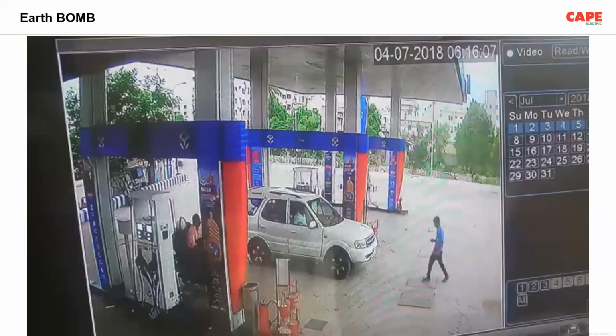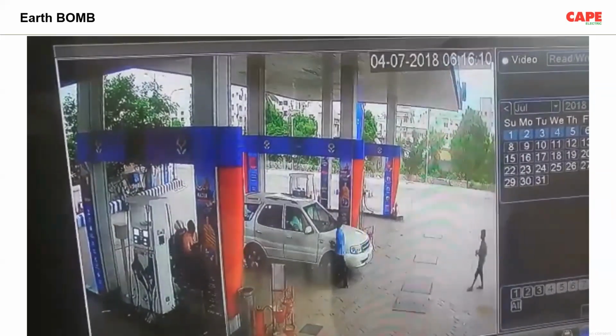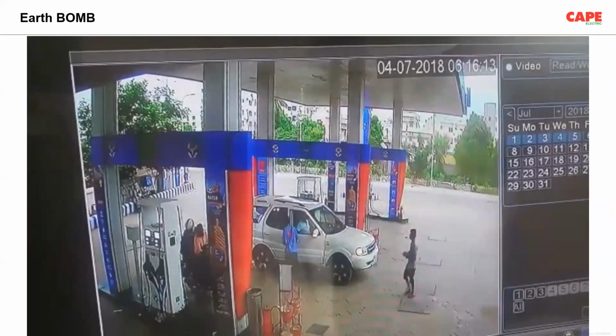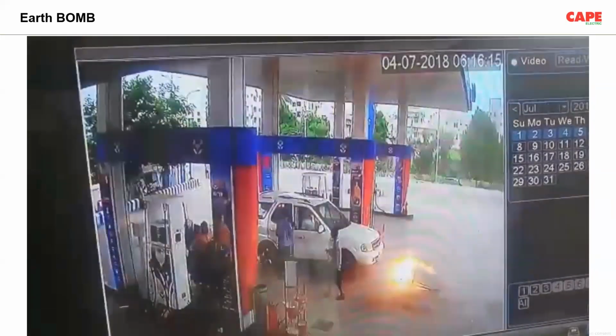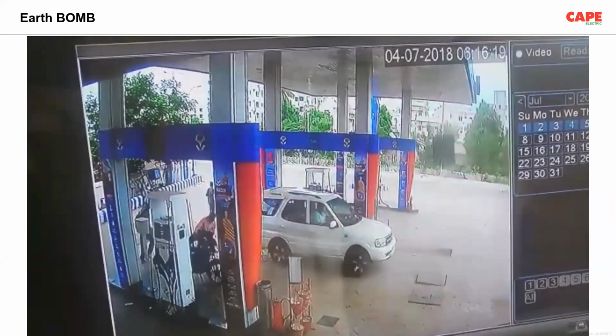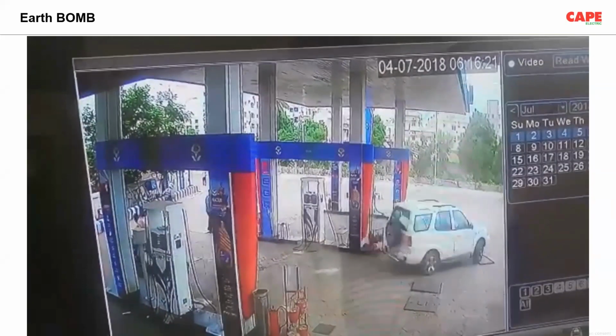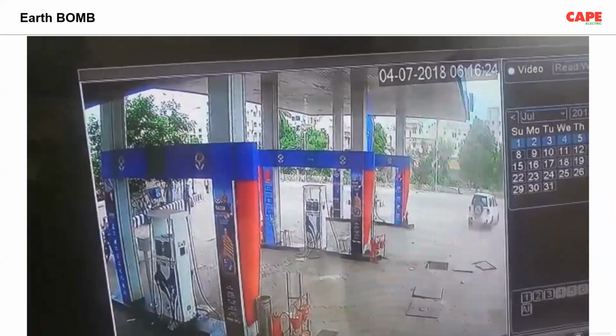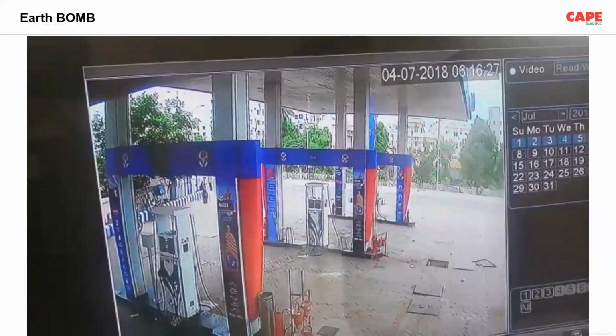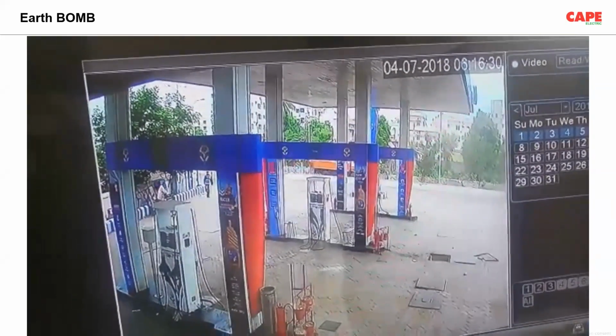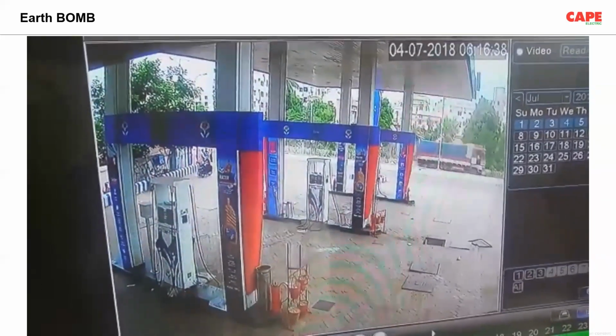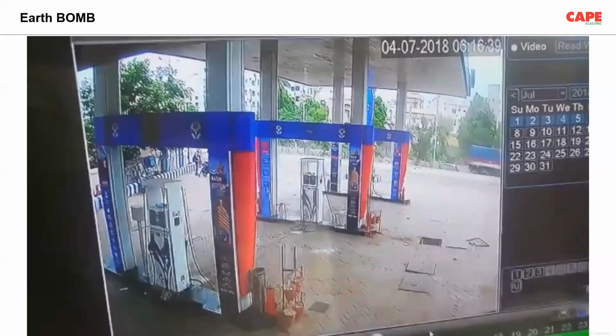I got a video saying that the MCCB didn't trip. There is a UPS, and the MCCB didn't trip during this incident. You can see some chambers: there is one blast, two blast, three blast, and the fourth one. I really don't know whether this is due to an earth electrode or not. Somebody sent it to me with a question saying this has happened but my MCCB didn't trip. I asked whether it was due to an electrical fault. They said yes, but I really don't believe this is a blast from that. This is not an earth bomb, so I don't think it is because of an electrical fault, but still I'm not 100% sure.